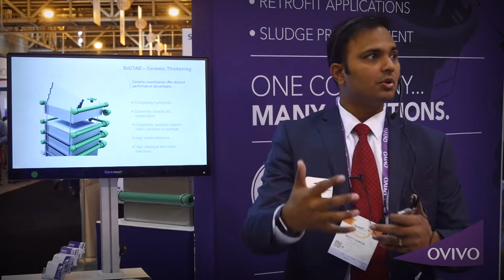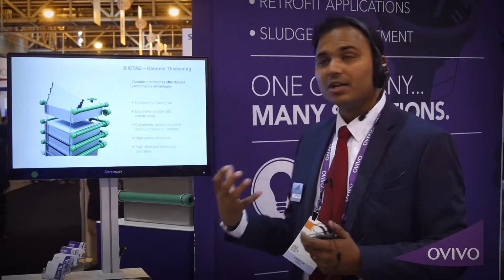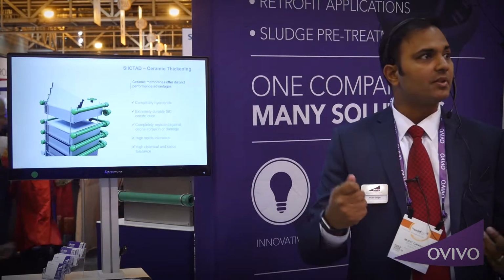Another cool way of thickening the sludge before going into aerobic digesters is using ceramic membranes. We have what is called the SiC TAD, or the silicon carbide thickening, where you have ceramic membranes which are used to thicken the sludge, and these are like your grandmother's china. It's unlike polymeric membranes, which can tear. You could pressure wash these to easily clean them, and we've been able to get very high fluxes, so you can have a very compact footprint to do your thickening rather than big thickeners or any other process. And it's very resistant to debris or any other solids that are in there, or to abrasion in general, because it's essentially one of the hardest substances known to man. And it's very tolerant to chemicals and other solids in your sludge. So it's a very efficient way to get about 3 to 4% solids out of your waste activated sludge, or from your RAS or WAS.